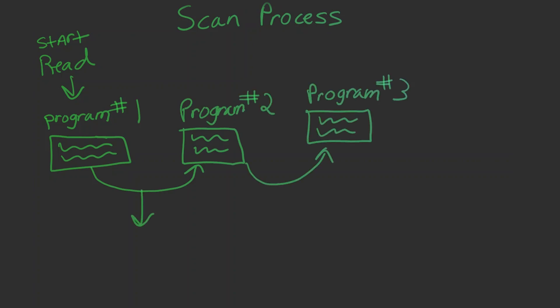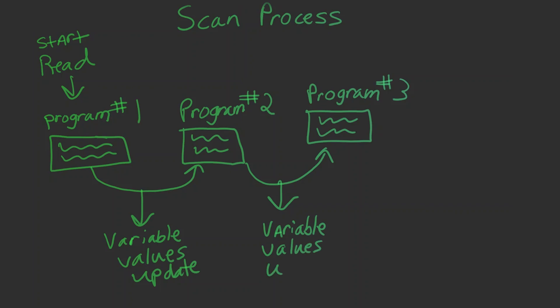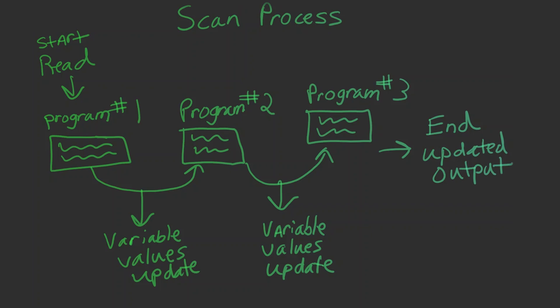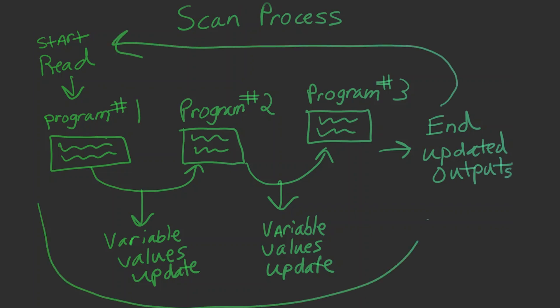As the individual programs are executed, variable values are updated to be used for subsequent programs. Finally, after all the programs have been completed, the controller updates the state of outputs on the controller and the process begins again. This entire process is called a scan, and it is normally performed several times a second, varying depending on the complexity of the programs.